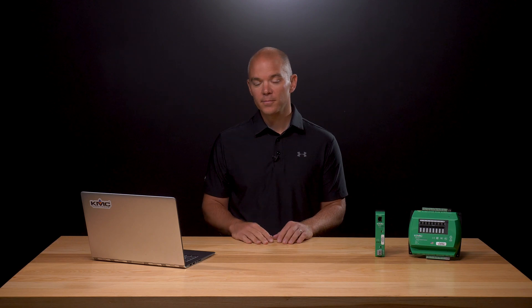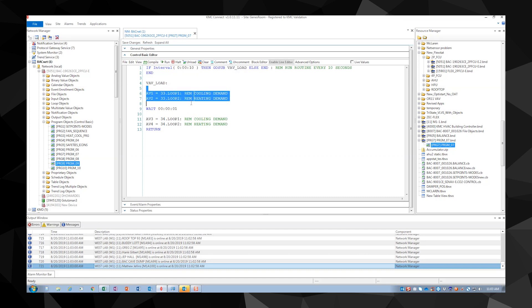In our first example, we need to know the total load of cooling and heating from each downstream VAV controller that is connected to an air handler controller. The first line states that every time 10 seconds goes by, we will run the subroutine VAV load. This routine reads the points that we have specified, loop 1 and loop 2, on the VAVs located at address 33 and 34 in our system.